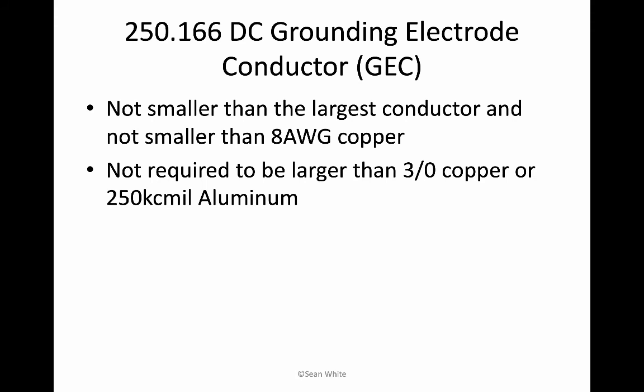It kind of brings me back to one of these memory techniques. 250.66 is your AC grounding electrode conductor. And then we put a 1 before the 66. 250.166 is the DC grounding electrode conductor. And then we put a 22 where the 66 goes. That's 250.122, and that's how we size our equipment grounding conductors. Sometimes with memory techniques like that, just remembering 66, 166, and then 122, we can get to things quickly.